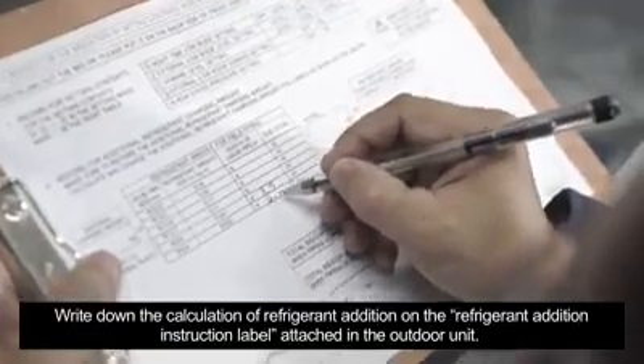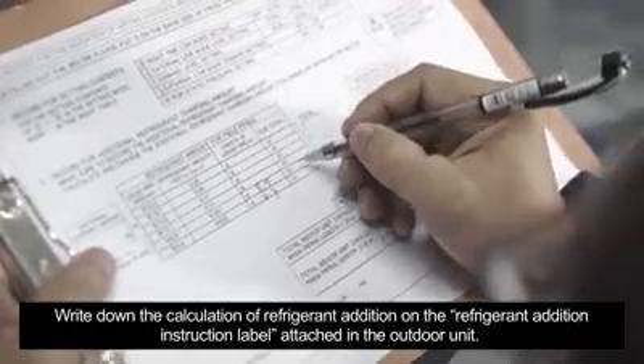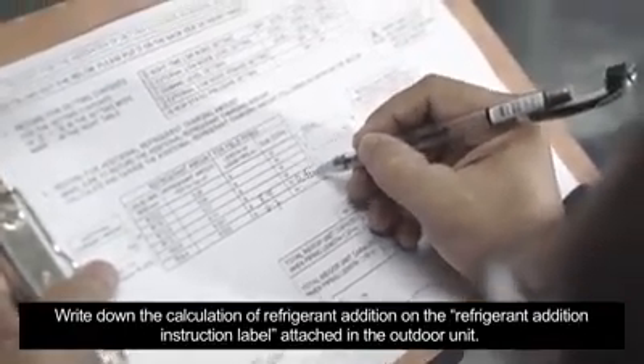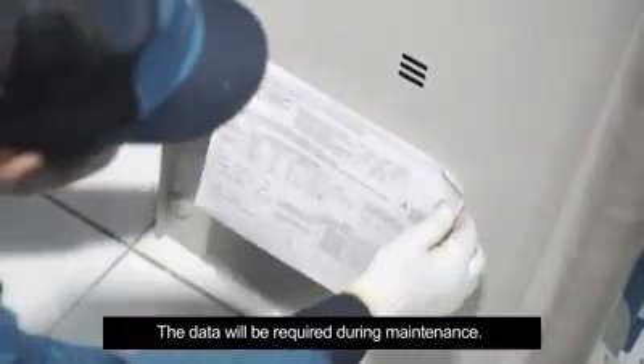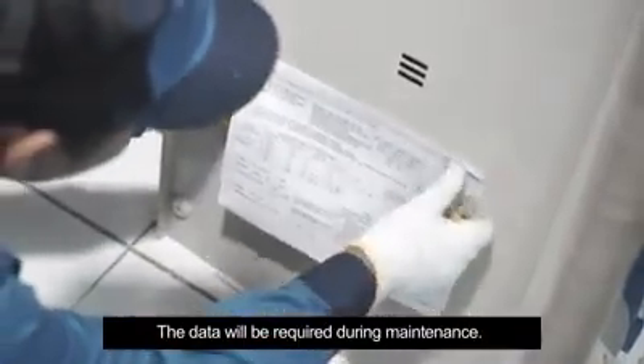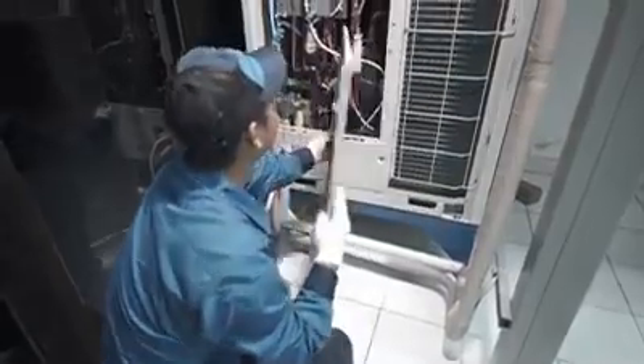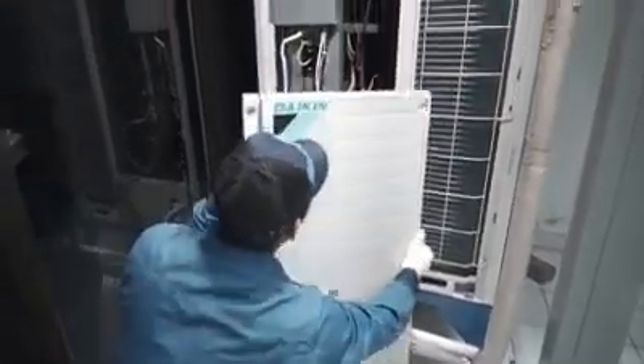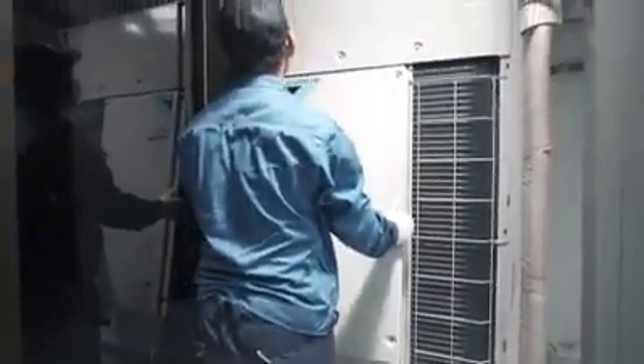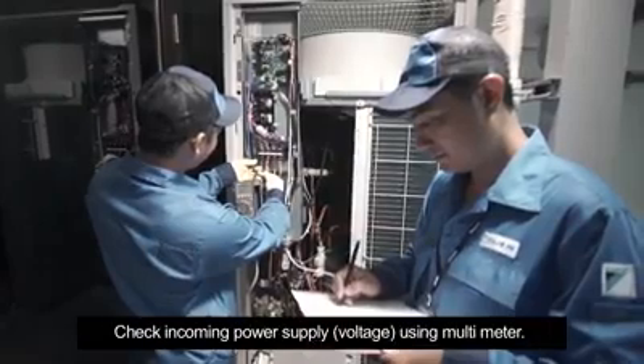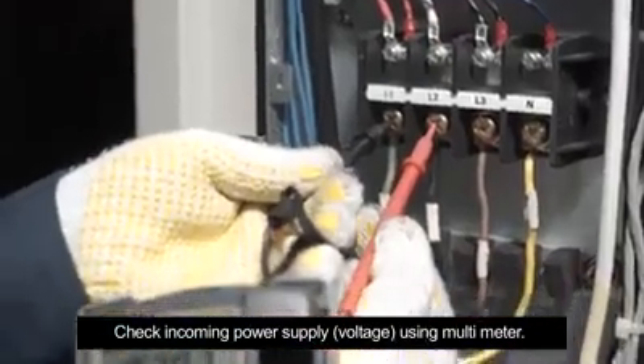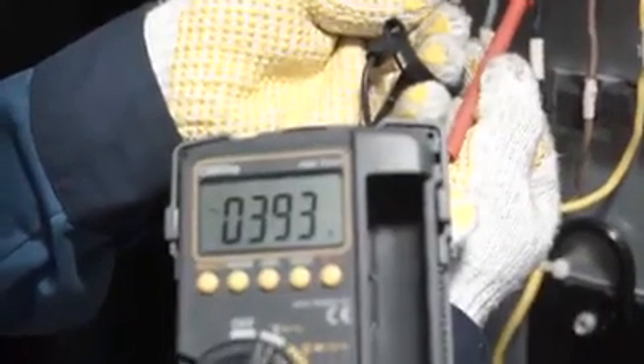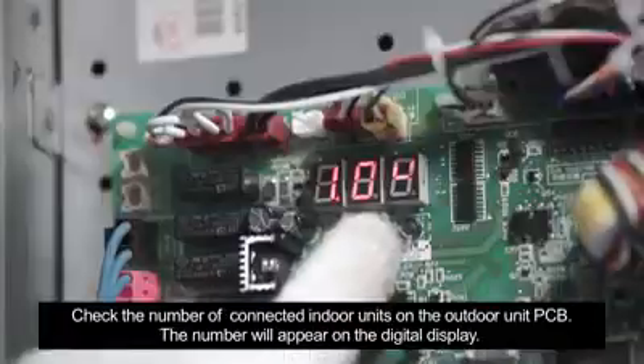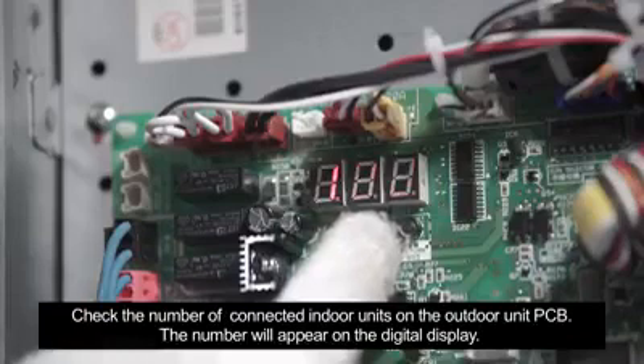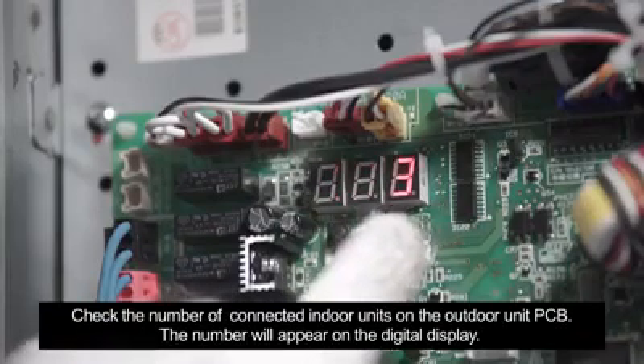Write down the calculation of refrigerant addition on the refrigerant addition instruction label attached in the outdoor unit. The data will be required during maintenance. Check incoming power supply using multimeter. Check the number of connected indoor units on the outdoor unit PCB. The number will appear on the digital display.